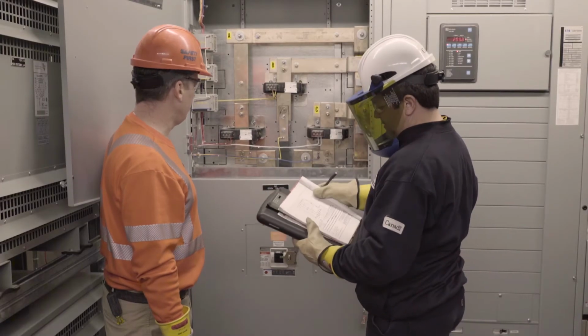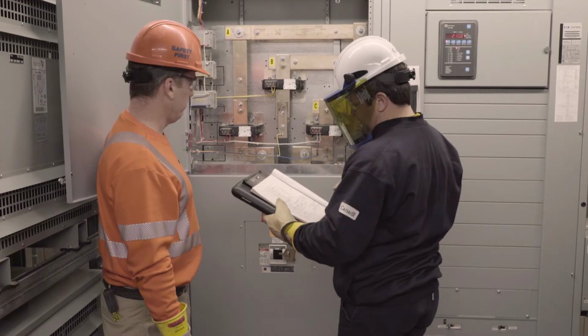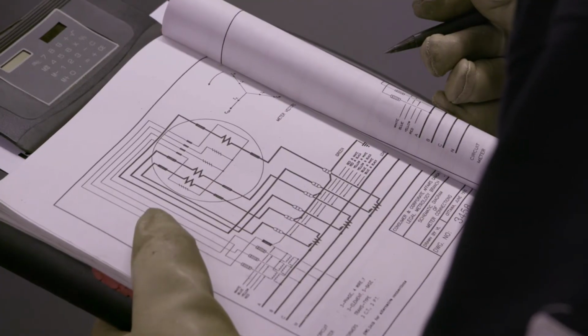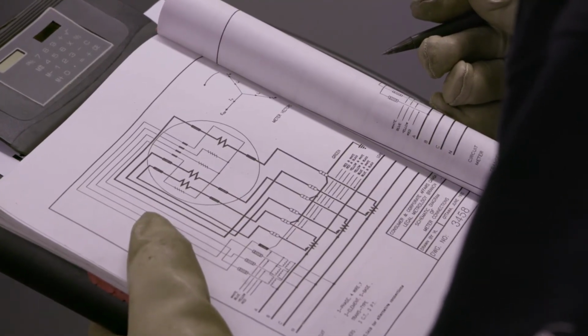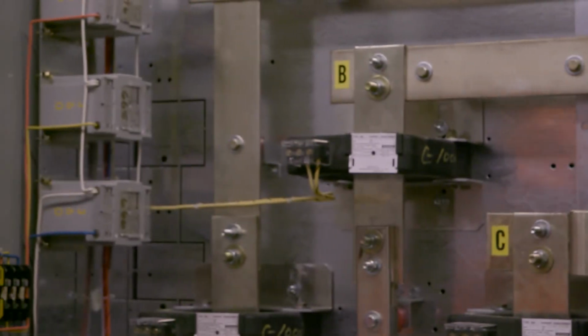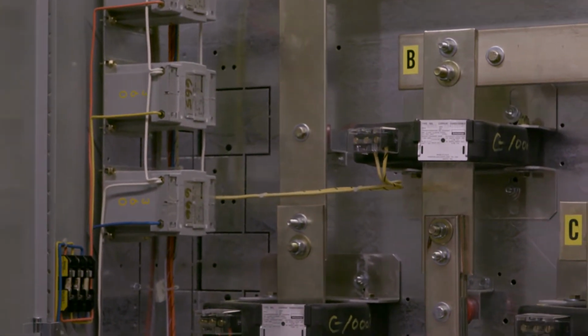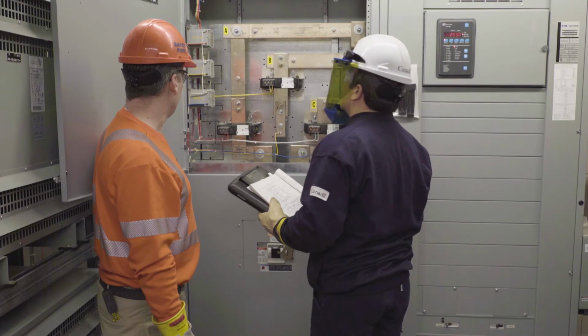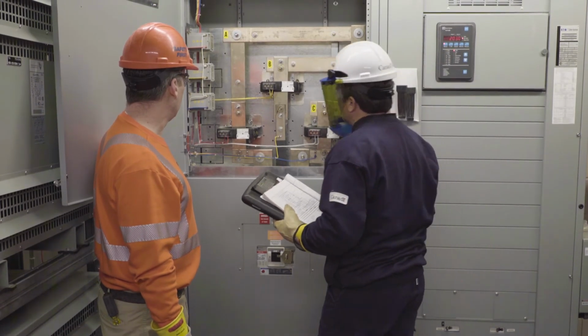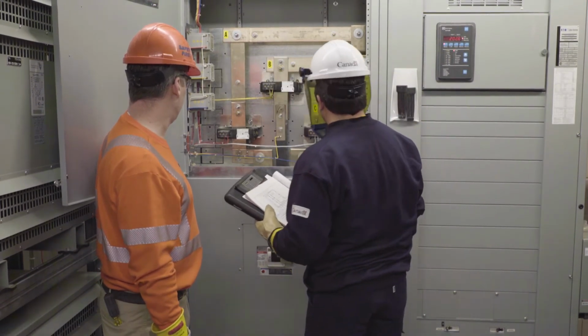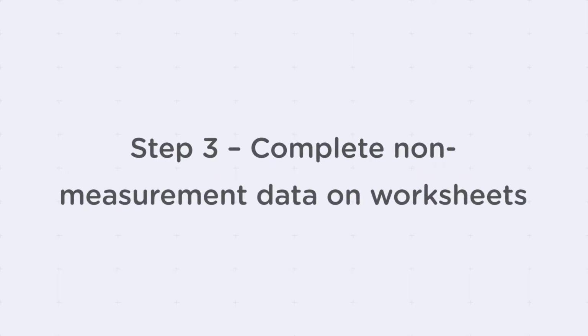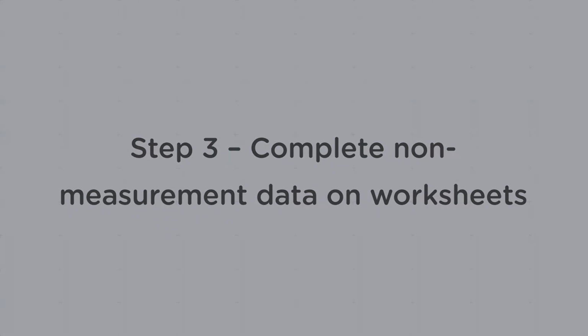Once the correct standard drawing is identified, visually verify that A. The installation is using the correct color code for all associated voltage, current, ground, and neutral connections, and B. All associated voltage, current, ground, and neutral wires are correctly connected as per standard drawing. Finally, complete all remaining non-measurement data on your worksheets.